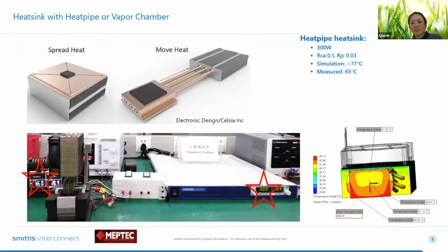So recently there's a lot of interest in moving to using vapor chamber or heat pipe into the manual lid for testing. The vapor chamber is used to spread the heat, but it is not ideal for manual test, especially since we need to design it to fit within this size of lid, as you see in the bottom. So the heat spreader is not ideal.